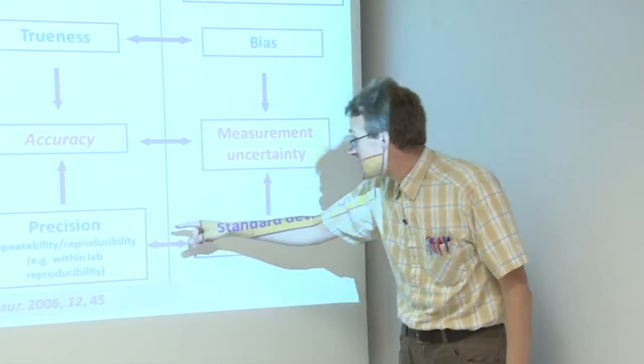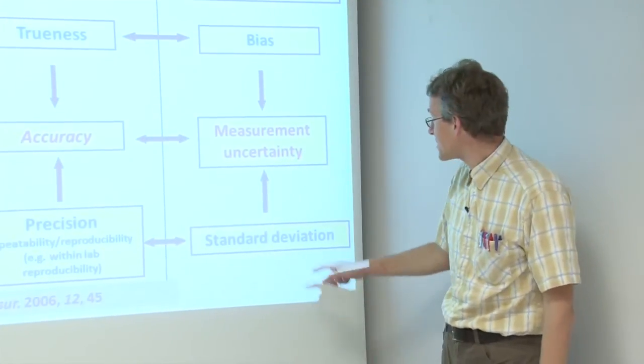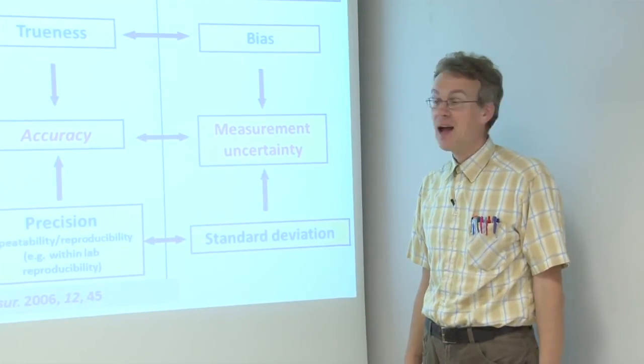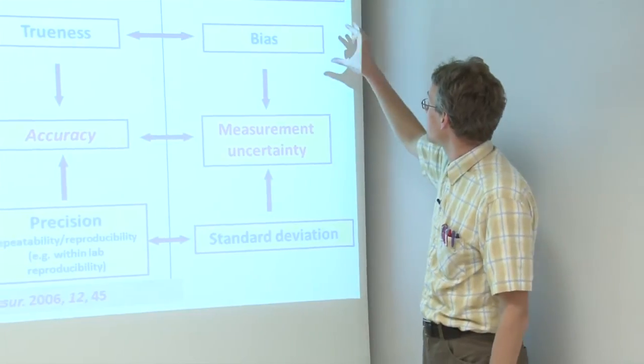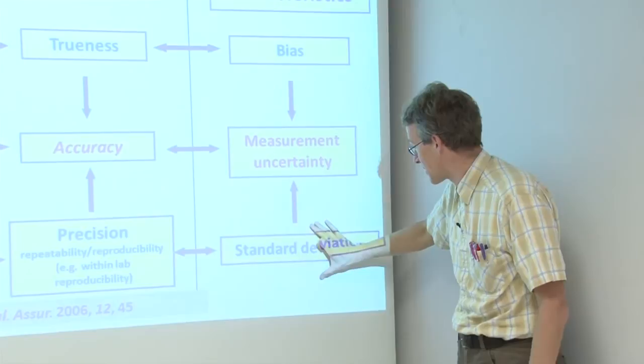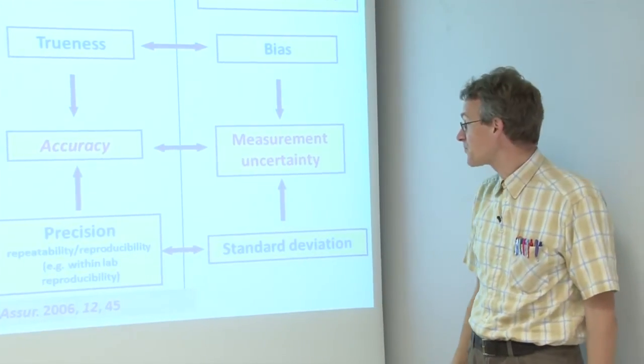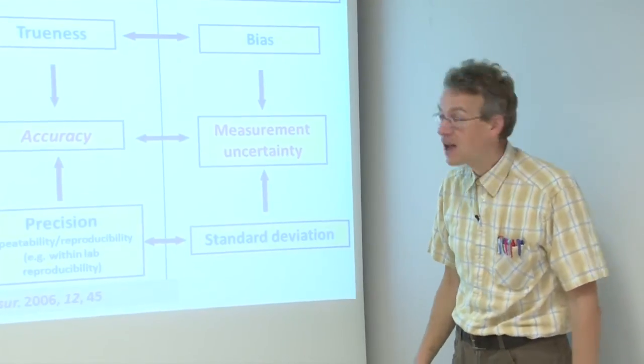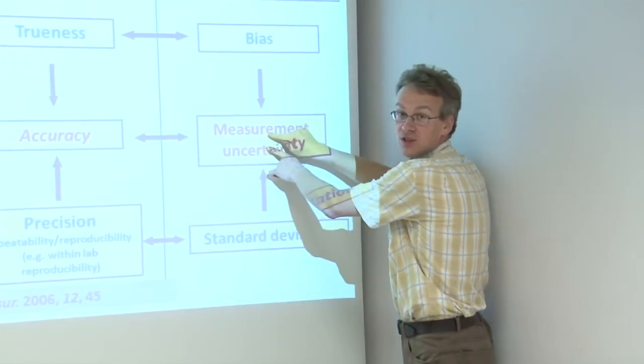And precision numerically is expressed by standard deviation of the repeated measurement results. And now it is possible to combine the estimate of bias and the precision standard deviation, if they have been found in a correct way, into measurement uncertainty.